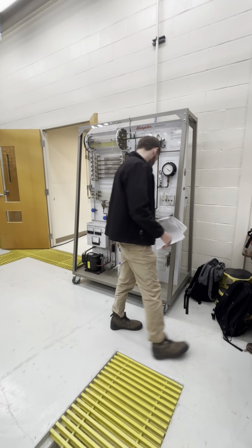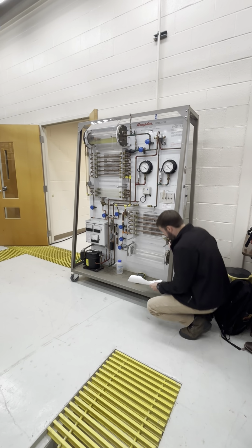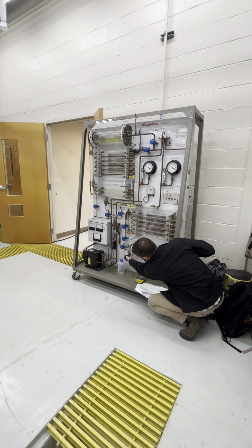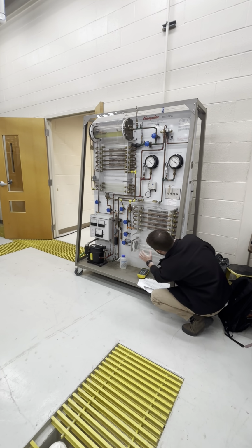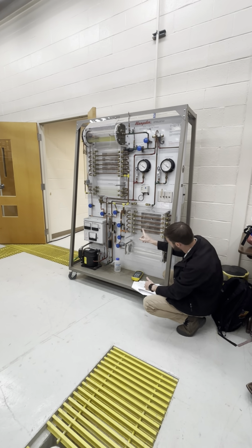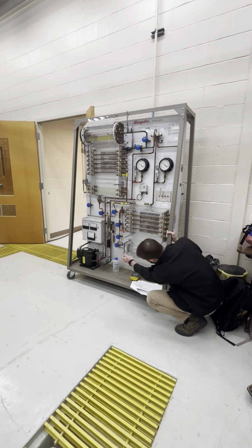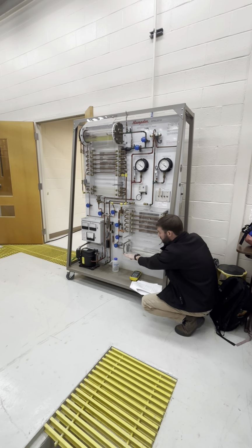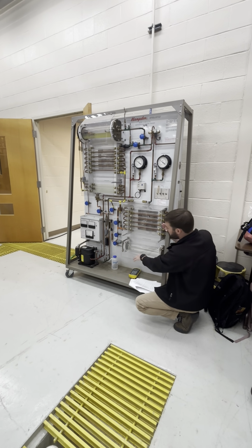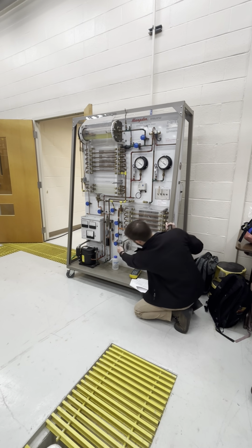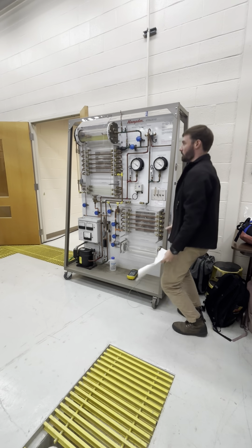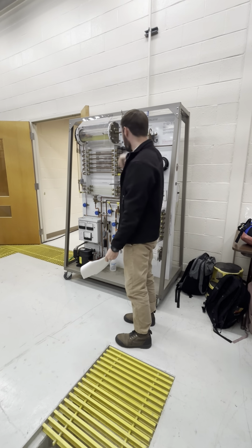I think I have enough in it. I'm going to check it one more time before we start next week. The liquid level here should be above the outlet right here. So the high pressure receiver, this component, basically just keeps those phases separate. It's going to come in as it condenses in the condenser, and it should draw straight liquid out of the bottom. Once everything hits steady state, this is going to drop a little bit as the fluid runs through the system. But if the liquid level goes below this, it starts to pull a little bit of air and you'll see a mixed phase in there. We don't want that. We'll have to stop it and pull some more into it.